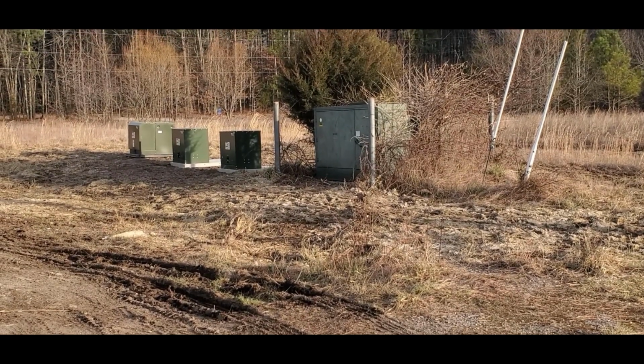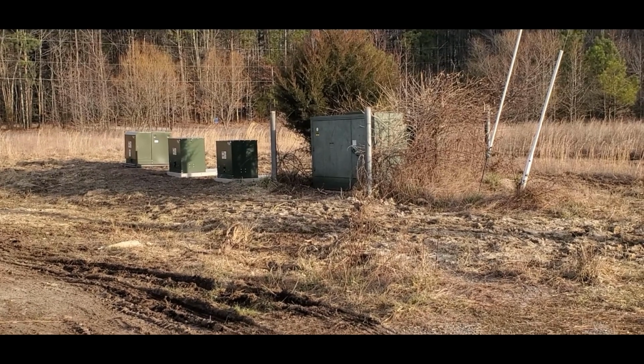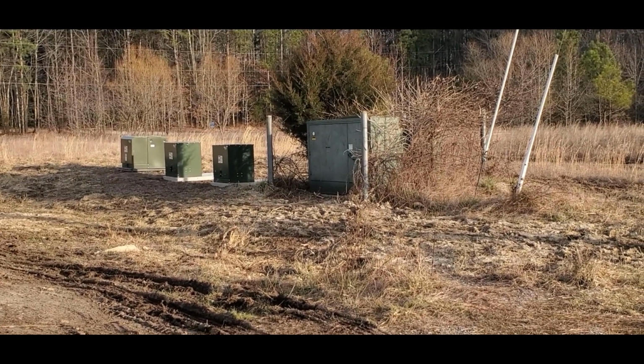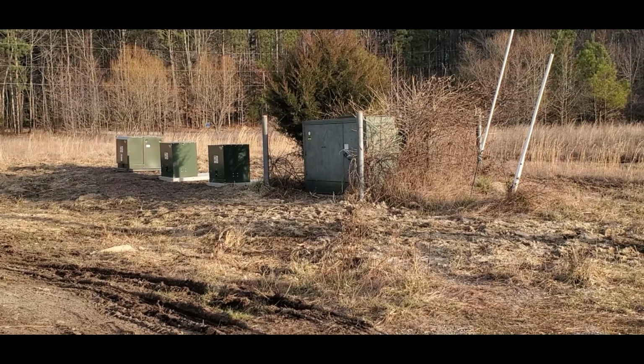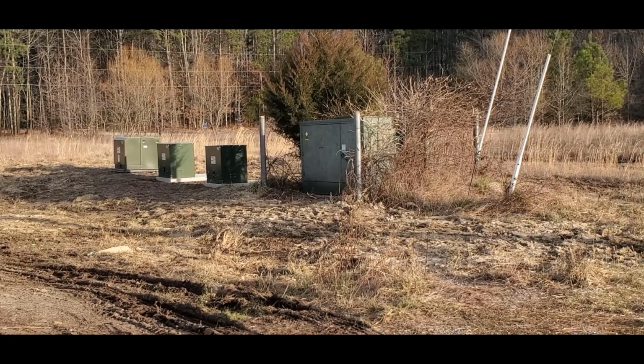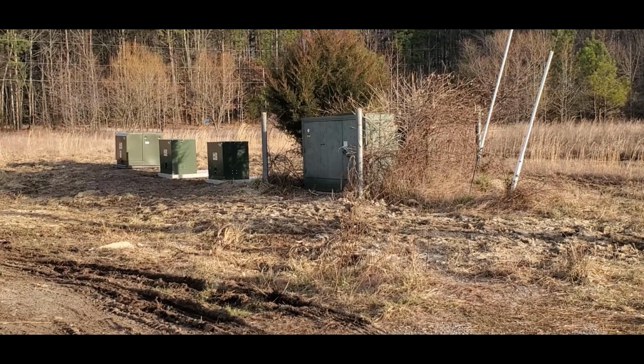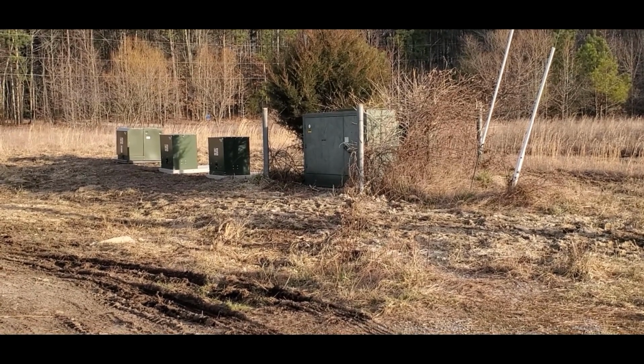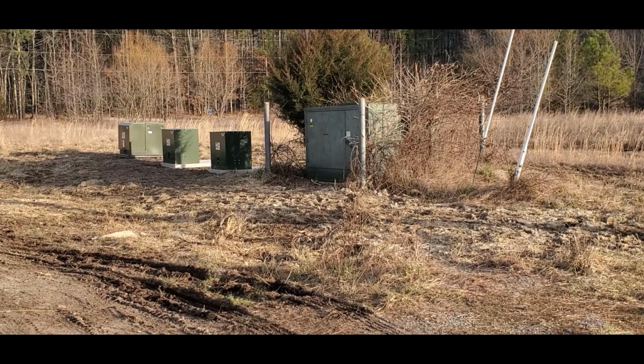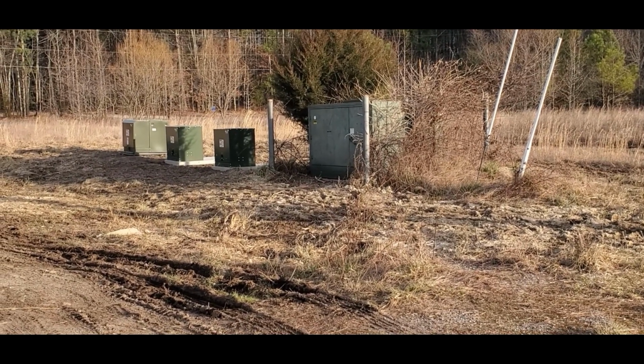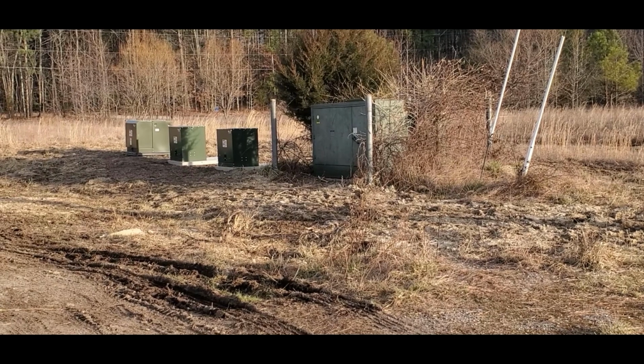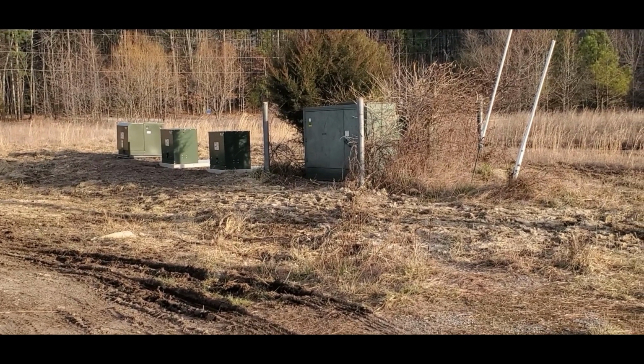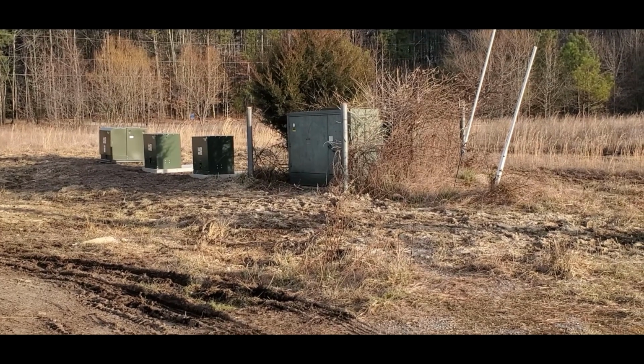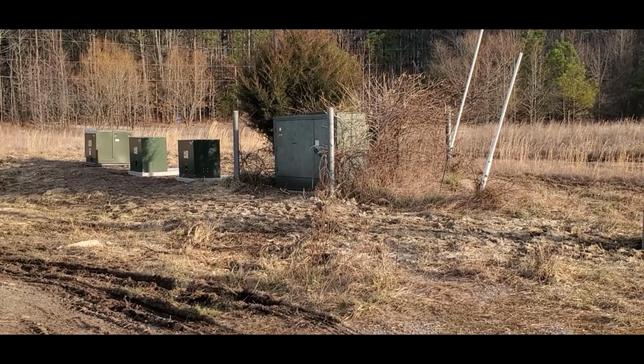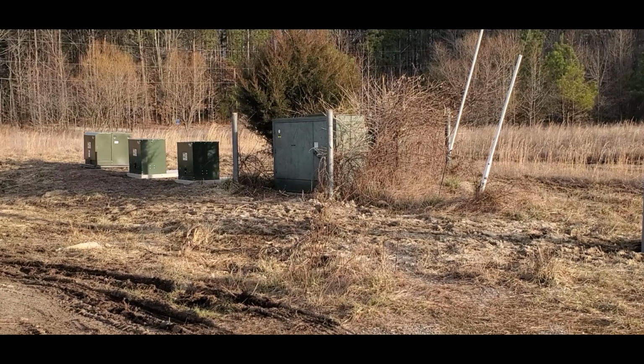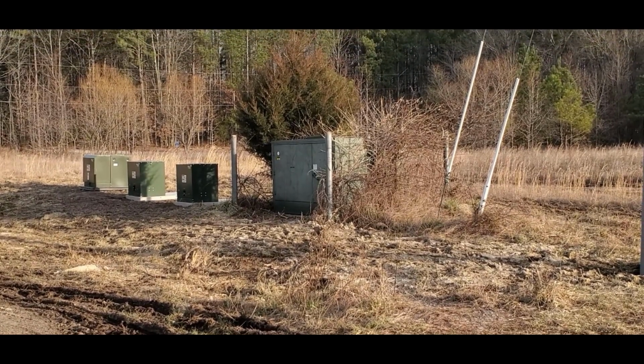so they don't plan on doing anything more, and I guess that includes leaving that old transformer in place, which after looking at the tags says that that's a 480 277 transformer, 750 kVA, 480 volt 277 transformer. The project manager told me that it was a 208Y 120 transformer. But big difference in what this sawmill was able to do running 480 volts versus running 208 volts. So I'm going to have to rethink the conduit sizes and how much power they were sending here and there around the building.